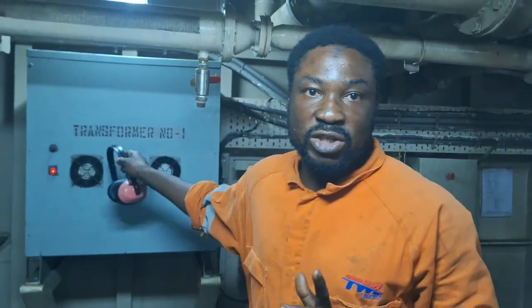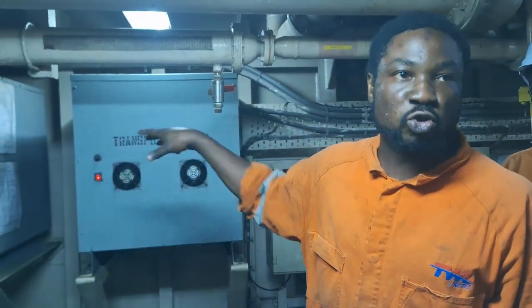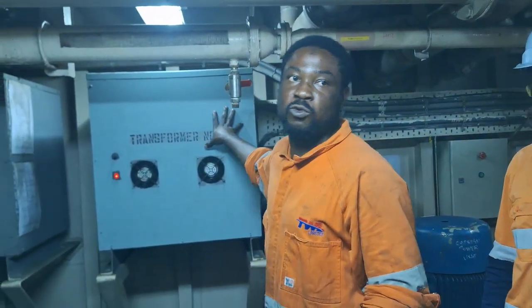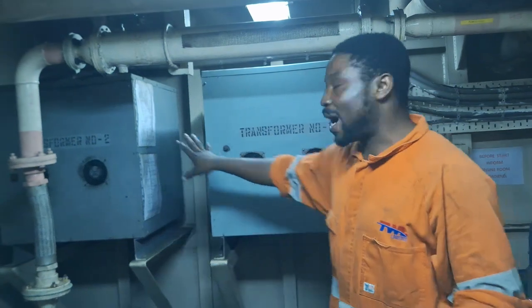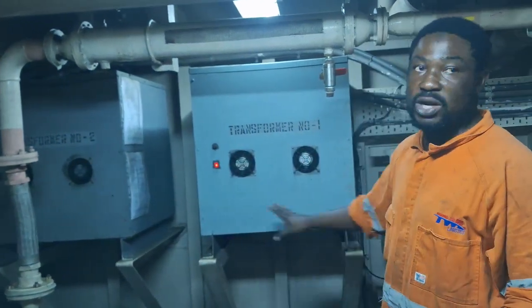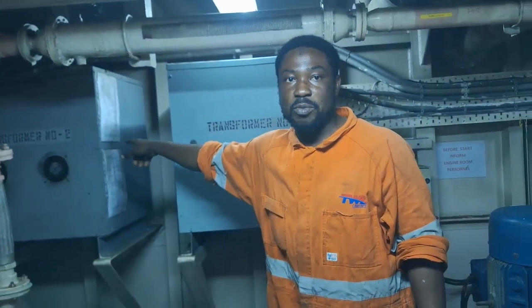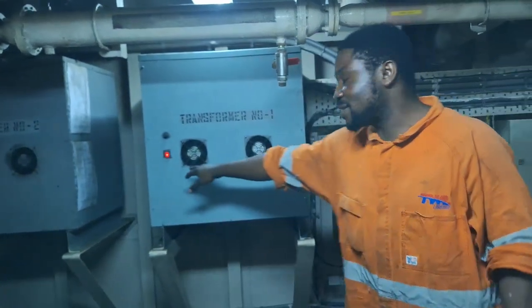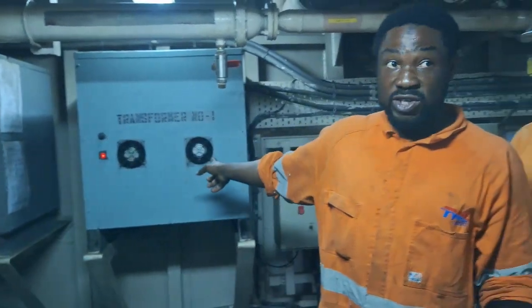Here we have the transformer. This is where the transformer is located. When you start up your engine, you get 415 volts, and the power is always concentrated to the MSB. From the MSB, we have some equipment which uses 220 volts. So we have the transformer that steps it down from 415 to 220 volts. These are transformer number one and transformer number two. This is a backup transformer - in case there's a problem, we can switch to transformer number two. Right now, as it stands, we are using transformer number one.